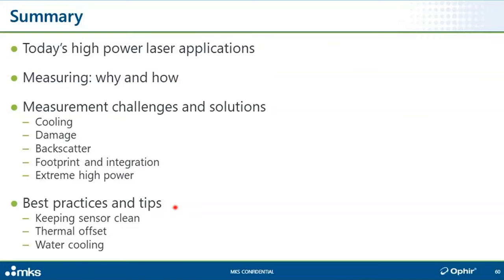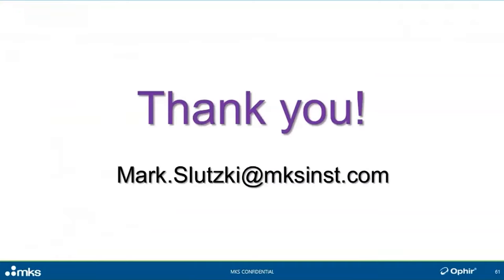Keeping the sensor clean is probably the best one. Be careful before you press the offset button. Wait till you're in thermal equilibrium. We said a few words about water cooling. More importantly, I pointed you in the direction of a very, very information-packed white paper on our website that deals with water cooling issues, water flow conditions, temperature, pressure, et cetera, and water type.